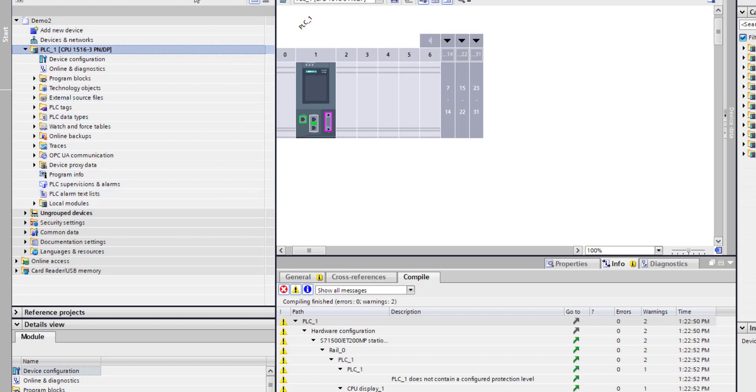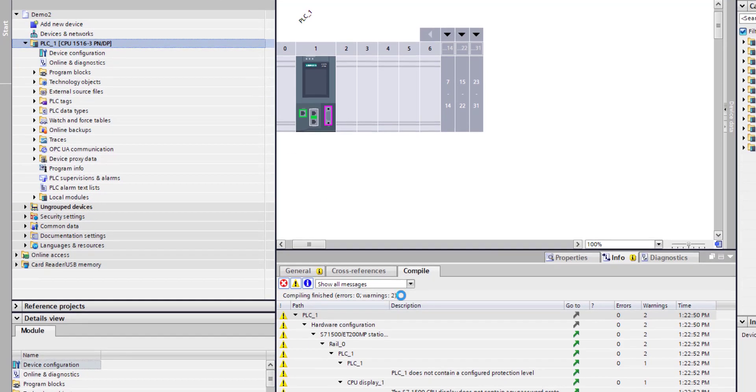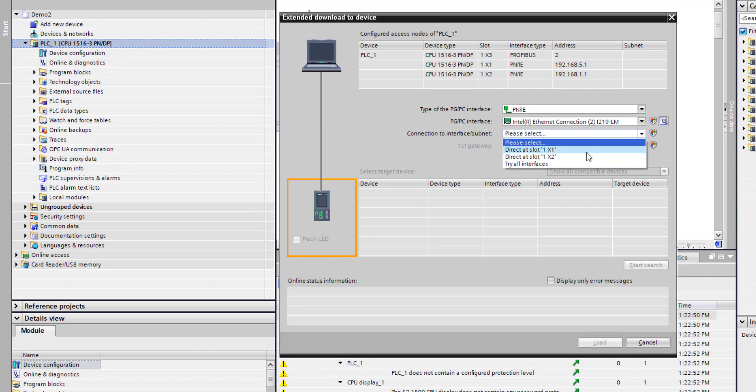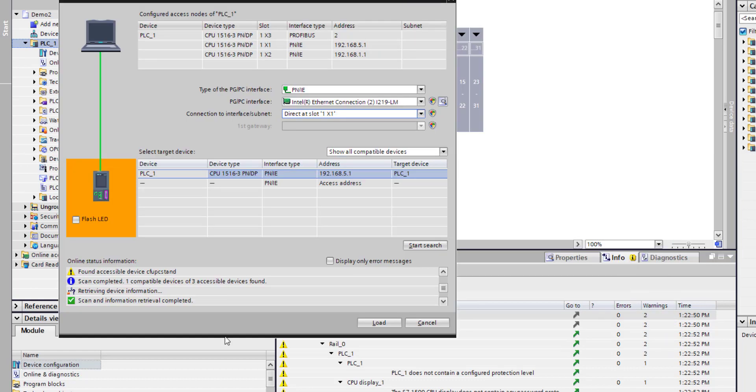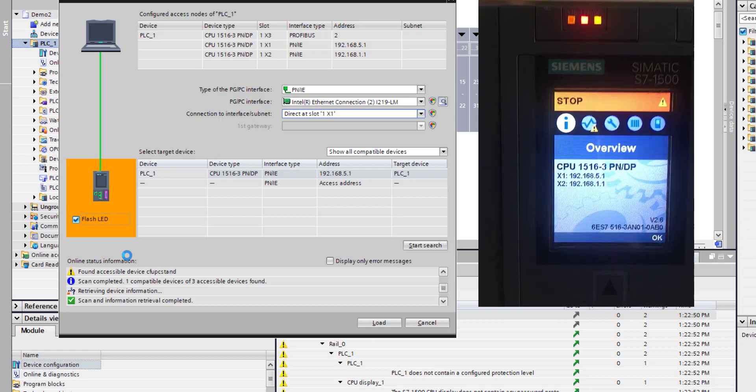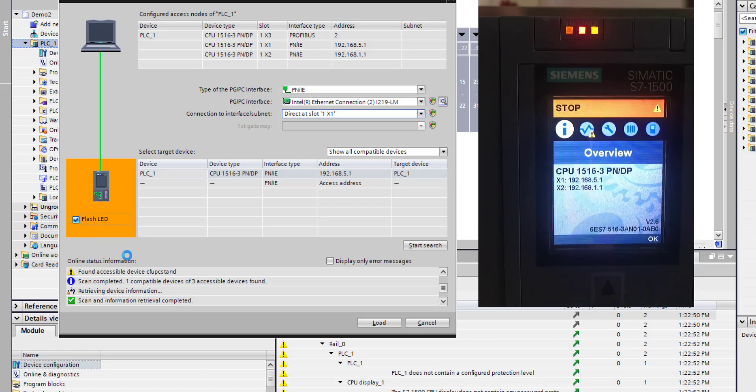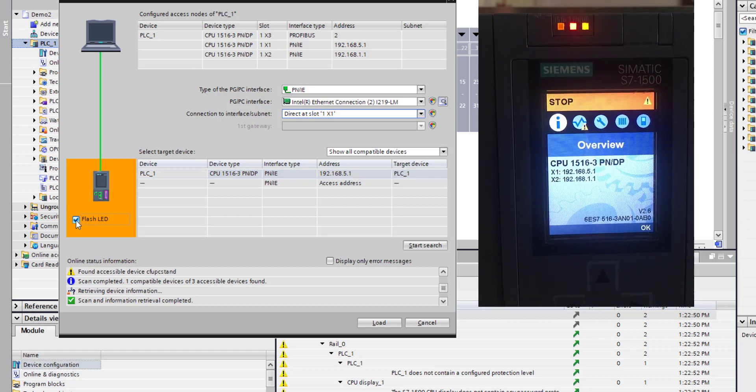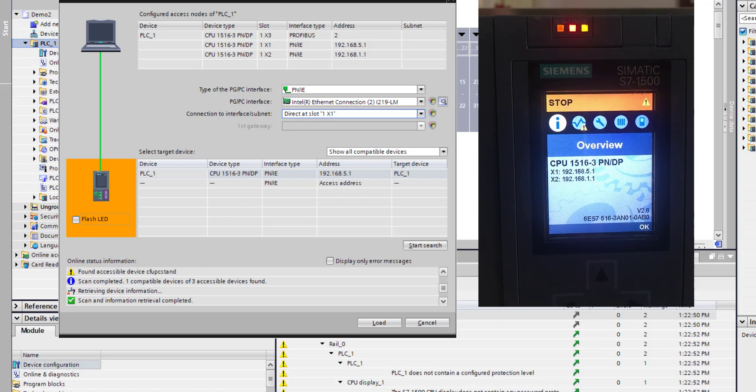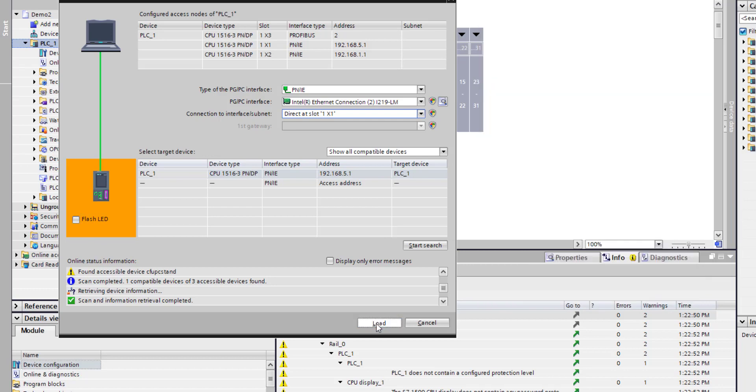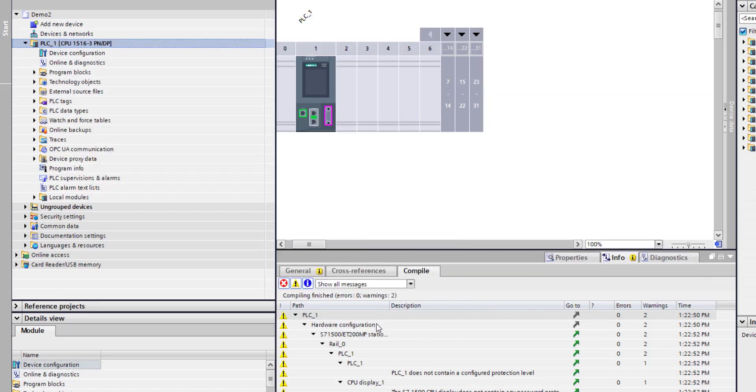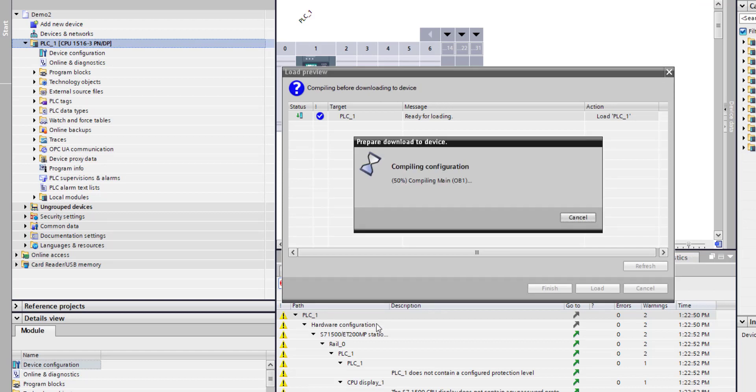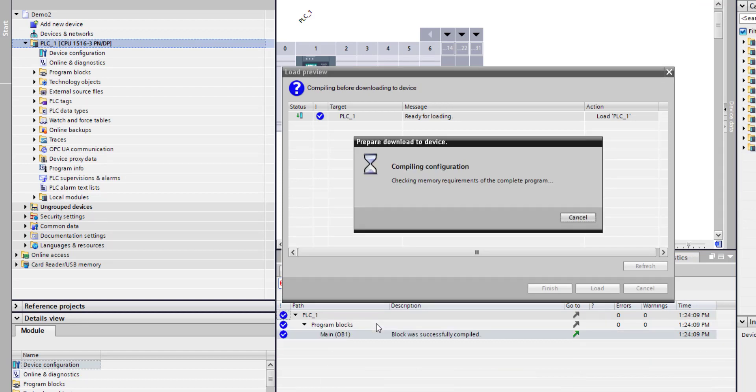Once I've compiled all the hardware, I need to do a download. We're going into slot one. What you can do just to make sure you're connected to the right PLC - just in case you've got multiple PLCs or a hot standby PLC or something like that - I can actually flash the three LEDs on the front of the unit to make sure I'm working on the correct one. I'll load that hardware and a blank OB1 to the PLC.